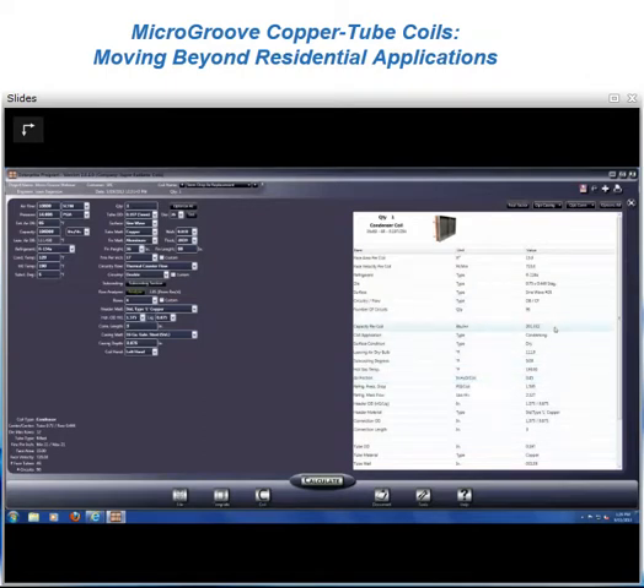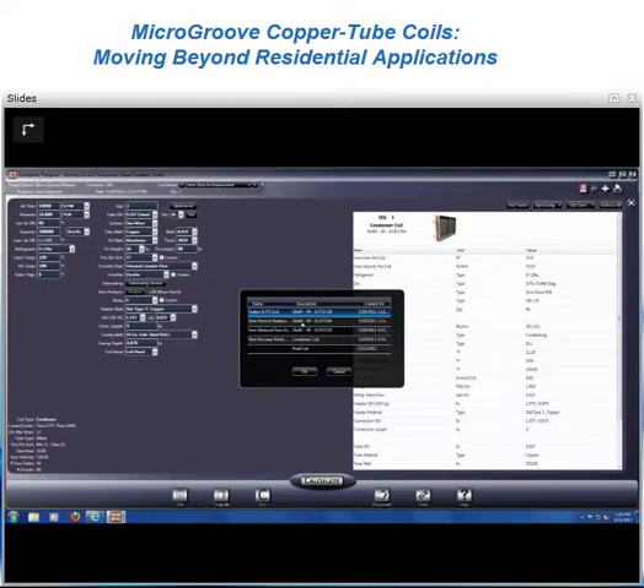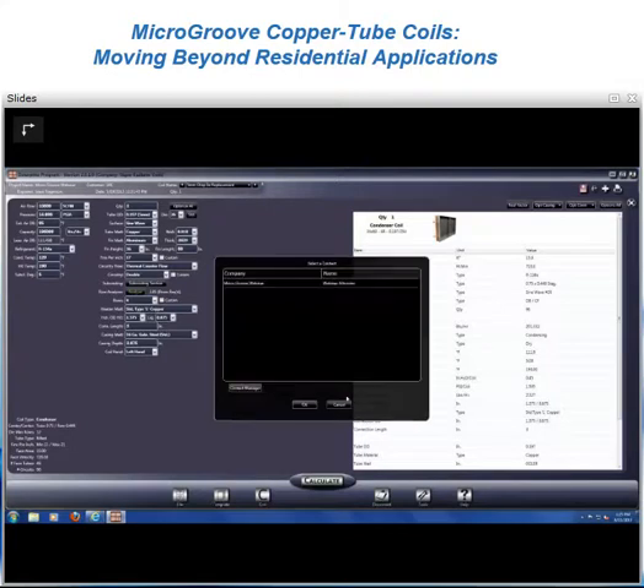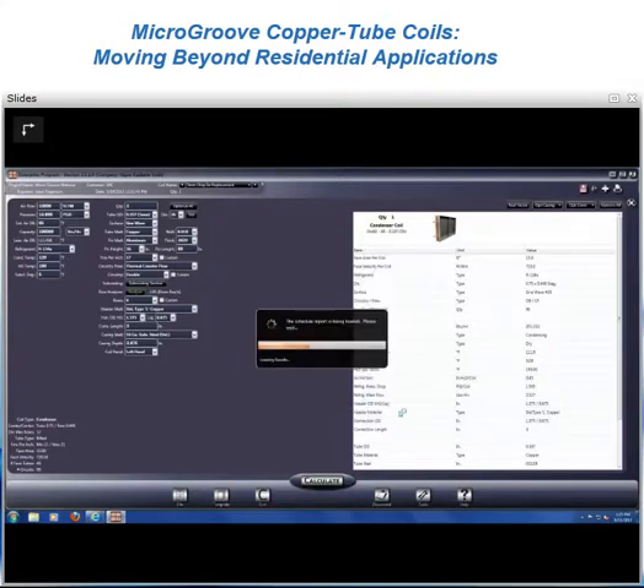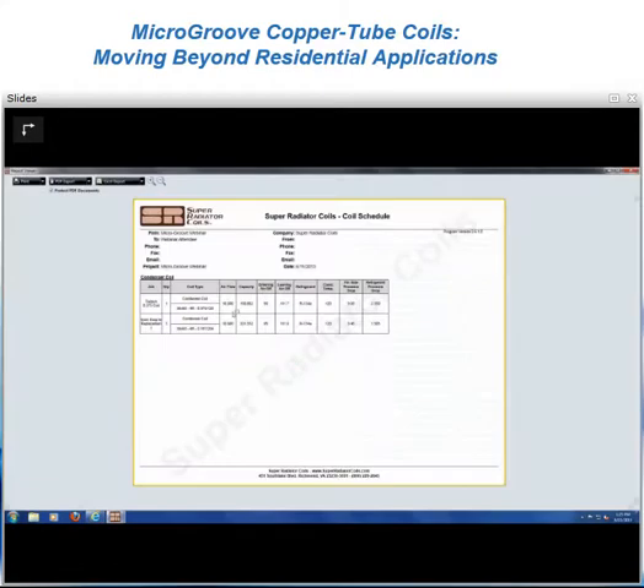and we see now that our performance is actually slightly better. It's 201,000 BTUs per hour, and the air friction is considerably less at 0.45. We can compare these side by side by creating a short schedule for our 3/8 tube coil and our 5mm drop-in replacement. We'll take a look at those quickly together. And what we can see is our capacity between the two coils is very much the same, as we would expect. The leaving air temperature is the same, condensing, but we've picked up a significant amount of air friction loss and the refrigerant pressure drop loss.